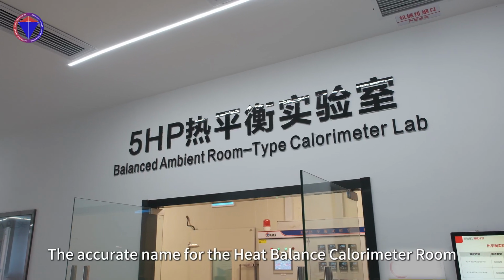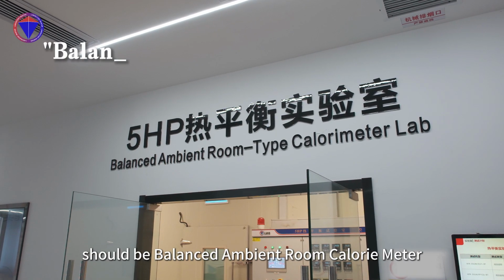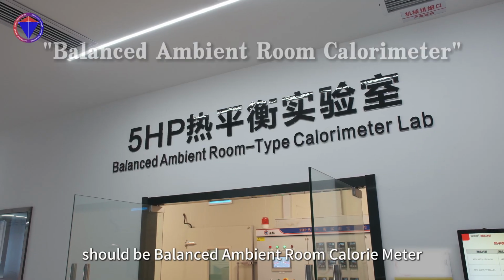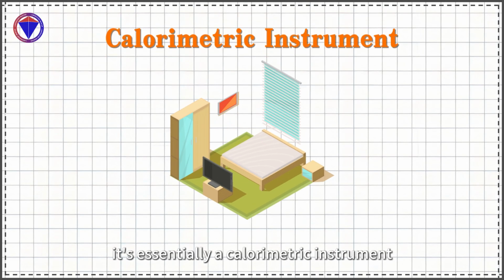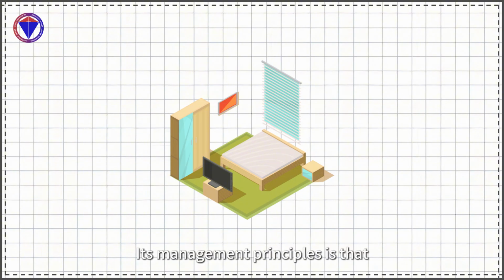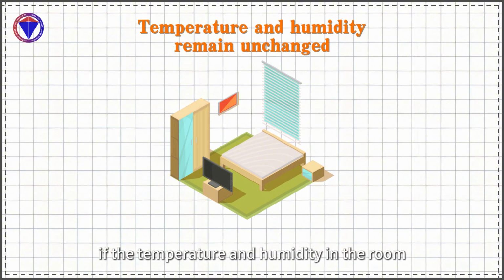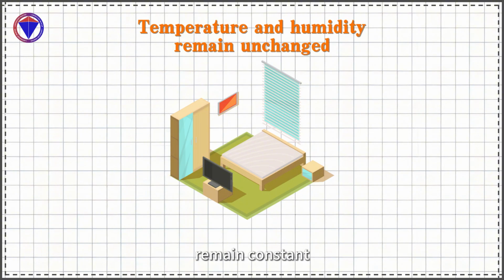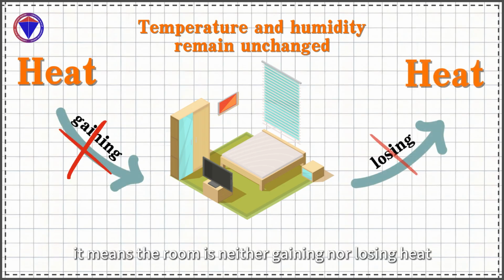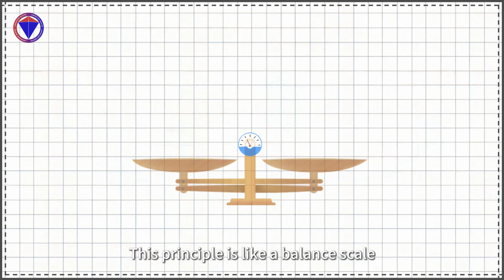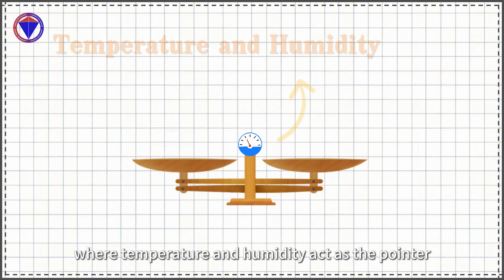The accurate name for the Heat Balance Calorimeter Room should be Balanced Ambient Room Calorimeter. As the name suggests, it's essentially a calorimetric instrument built from rooms. Its measurement principle is that if the temperature and humidity in the room remain constant, it means the room is neither gaining nor losing heat. This principle is like a balance scale, where temperature and humidity act as the pointer.